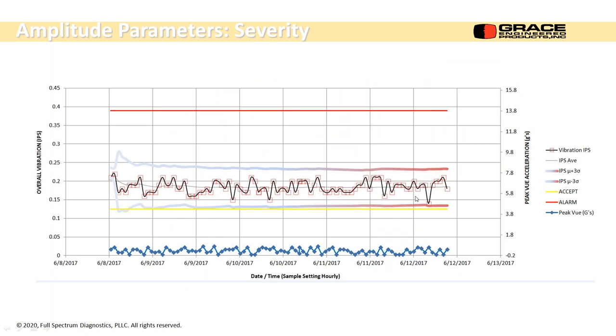Okay. I mentioned earlier the Grace nodes, they have a triaxial MEMS accelerometer in them. Two of those axes, the X and Y directions, I believe the frequency range is 1,000 hertz. The third direction, they're starting to change out those and make that, I think, an 8,000 or 9,000 CPM or hertz signal. So they're going to have better capability in the transducers they currently have. They're going to be able to monitor the X, Y, and Z low frequency range. Plus, they can do some sampling and bandwidth filtering to be able to get the really high frequency usefulness out of them. So 5 kilohertz up to 8 kilohertz or whatever the limit is on these. So that's a nice development way to go.